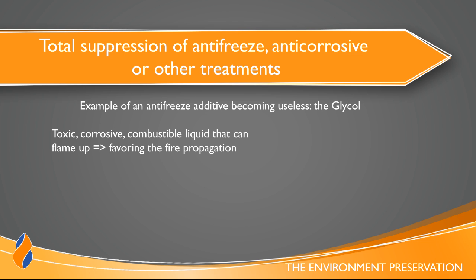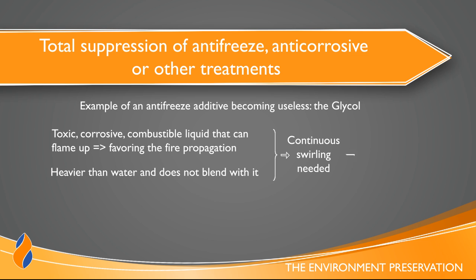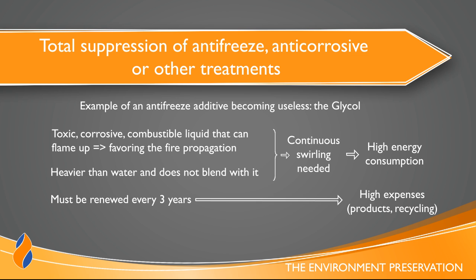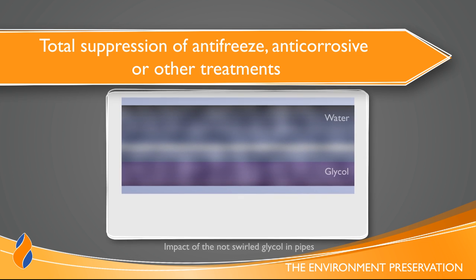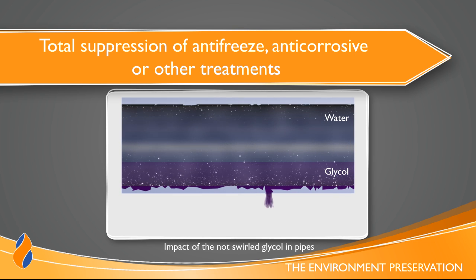Let's take the example of glycol, which is a toxic corrosive combustible that can flame up, favoring then the fire propagation. It is heavier than water and does not blend with it. Those properties require a continuous swirling of water, which leads to high energy consumption. Additionally, it must be renewed every 3 years, resulting to high expenses for product recycling and purchasing. If the glycol is not swirled, it deposits in pipes, creating corrosion and so risk of leak.